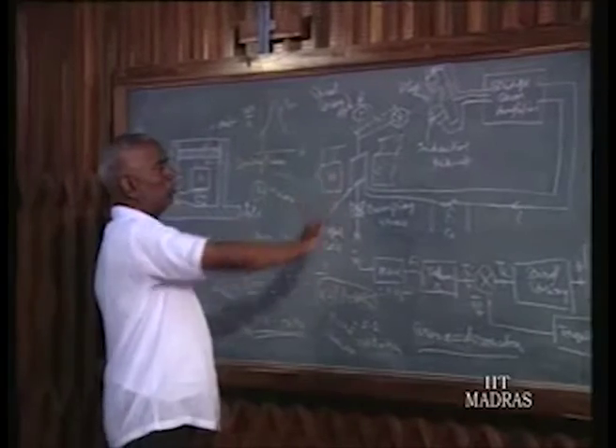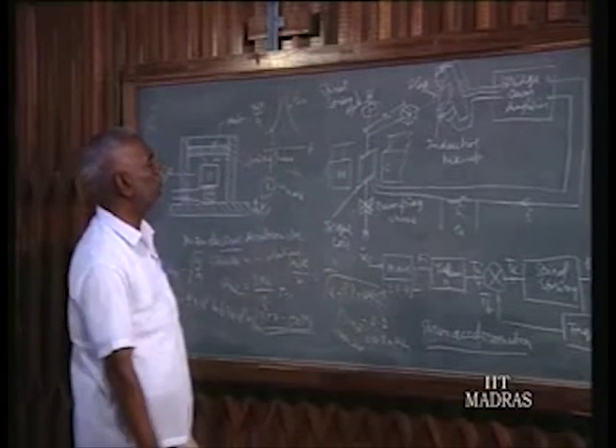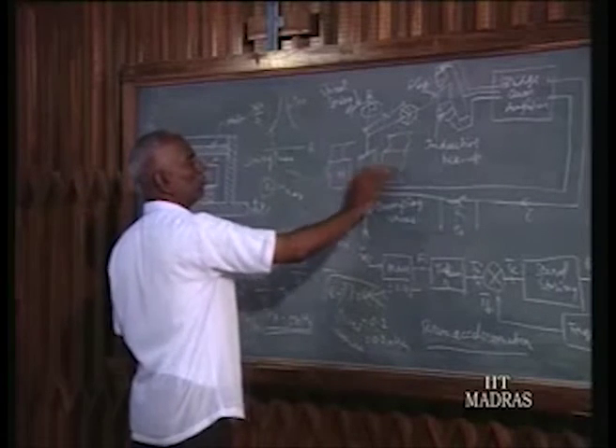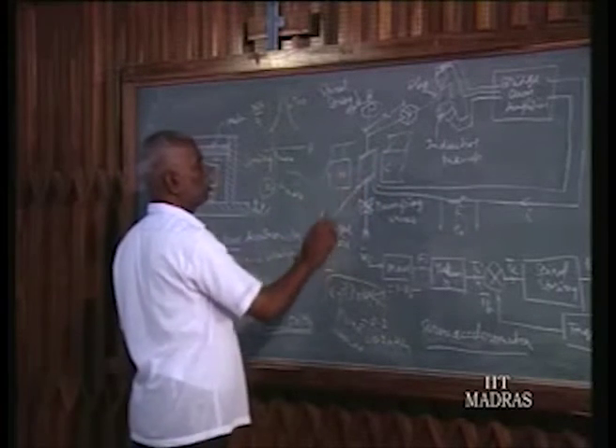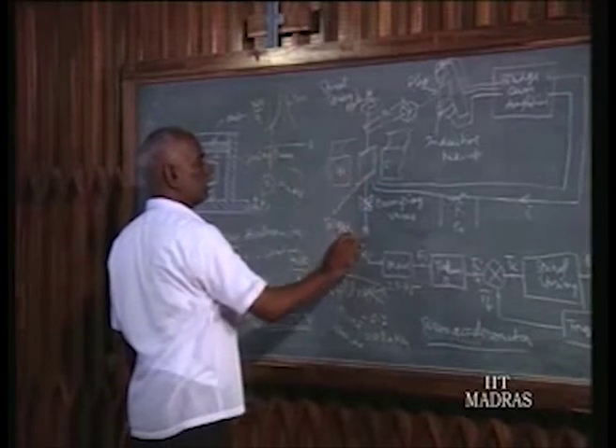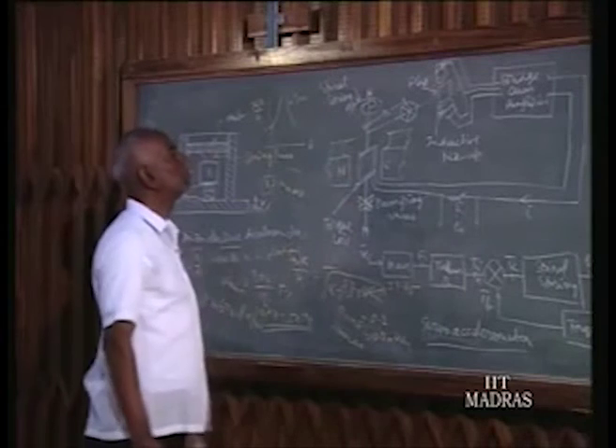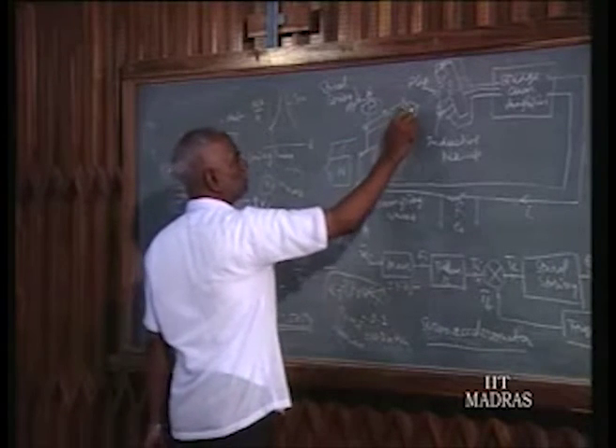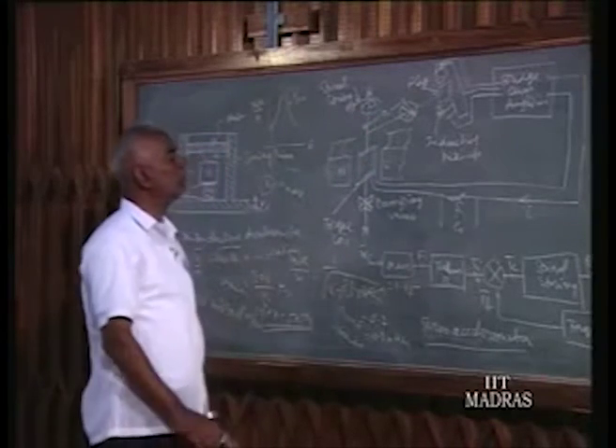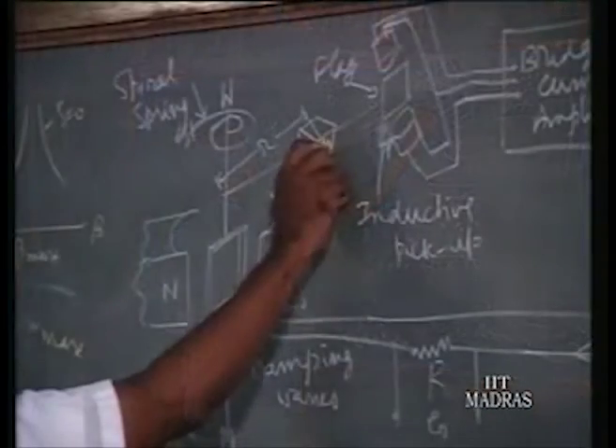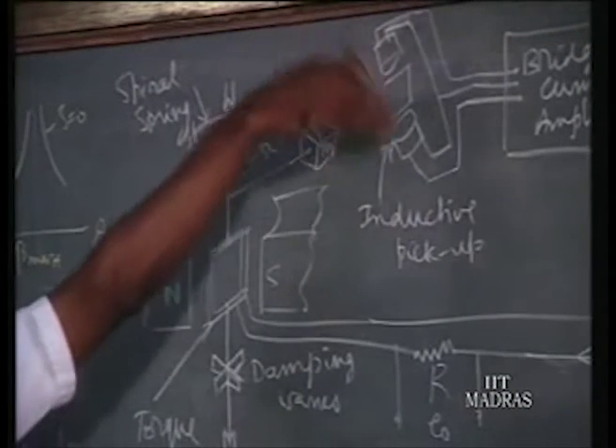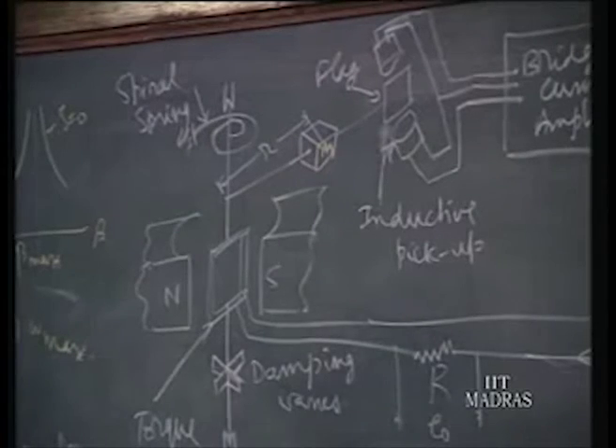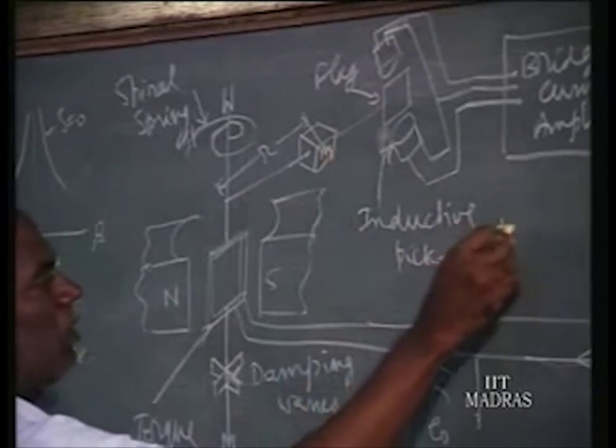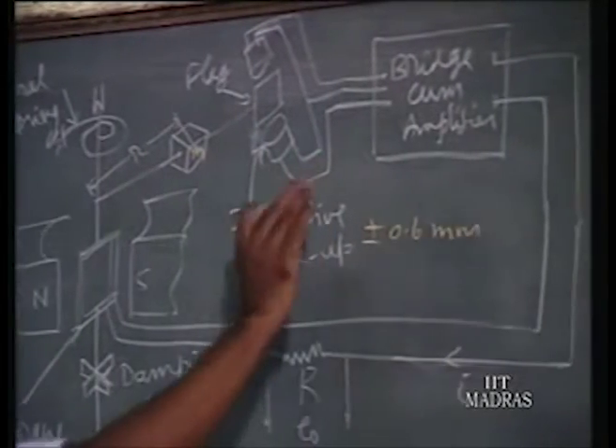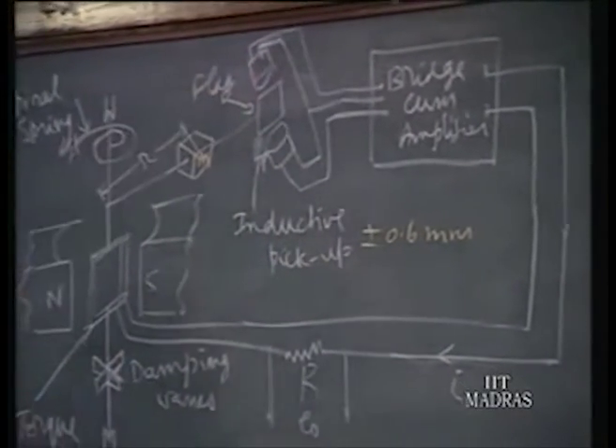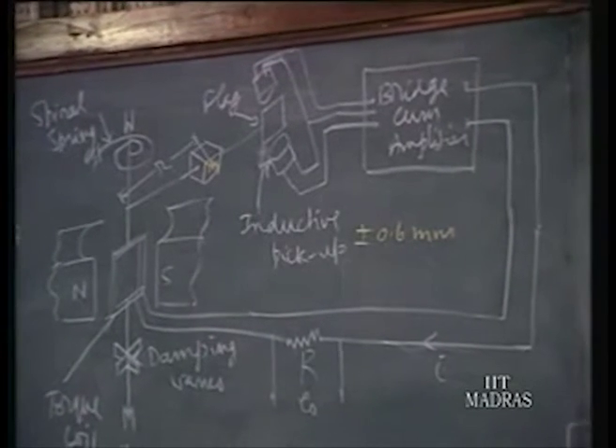Here the basic construction is being sketched. A coil is there in between a permanent magnet, it is called a torque coil, and that is mounted on two pivot bearings with its axis. To the axis, the mass is attached to a lever connected to the axis of the coil, and at the other end we have a flag which is moving in between two inductive pickups. We know with inductive pickups we can measure motion up to plus or minus 0.6 mm or plus or minus 1 mm. So actually they will be very close, but I have drawn like this just for explanation purposes.